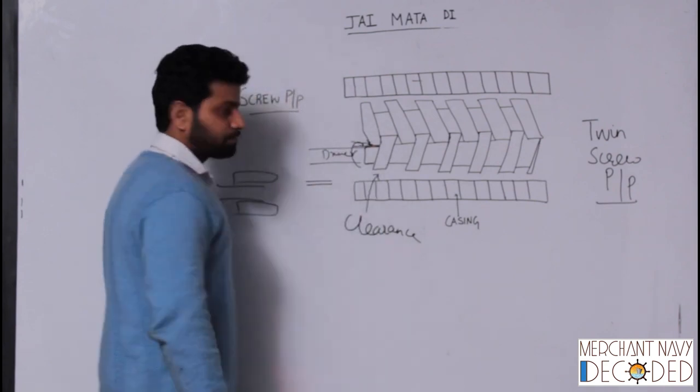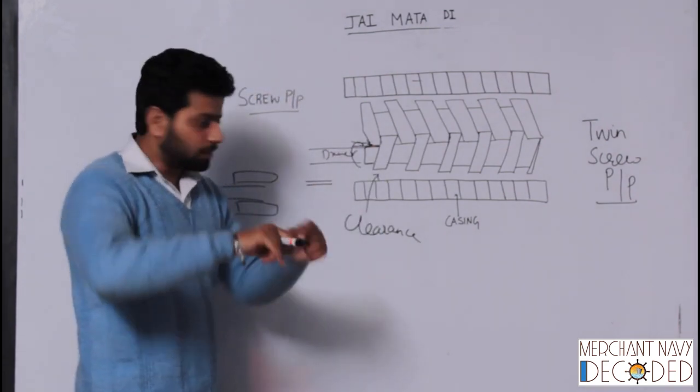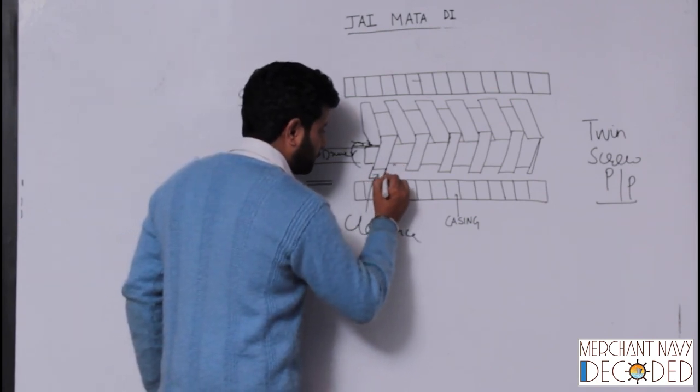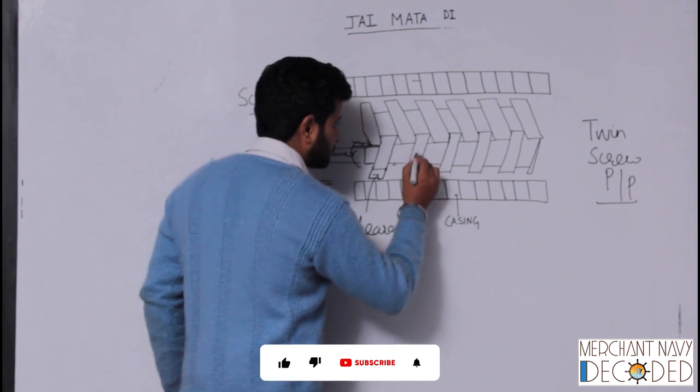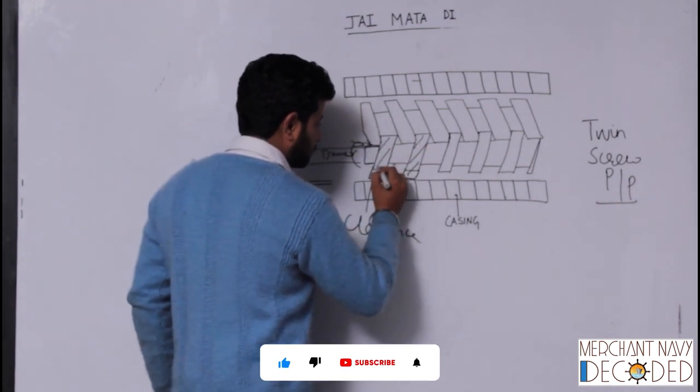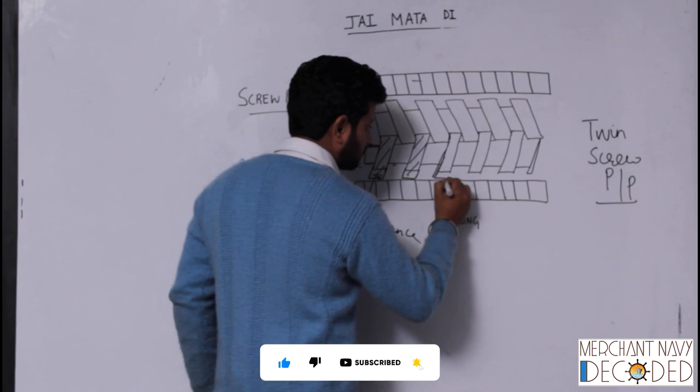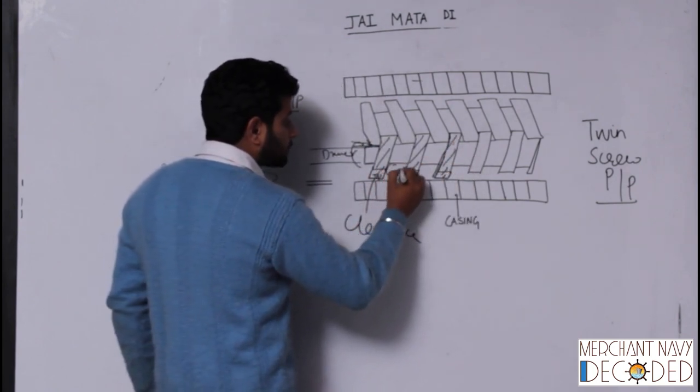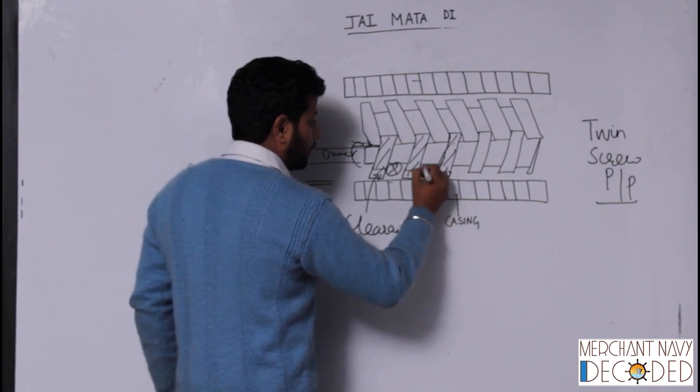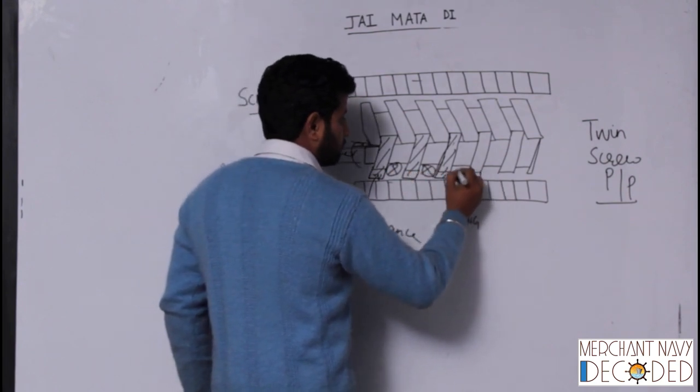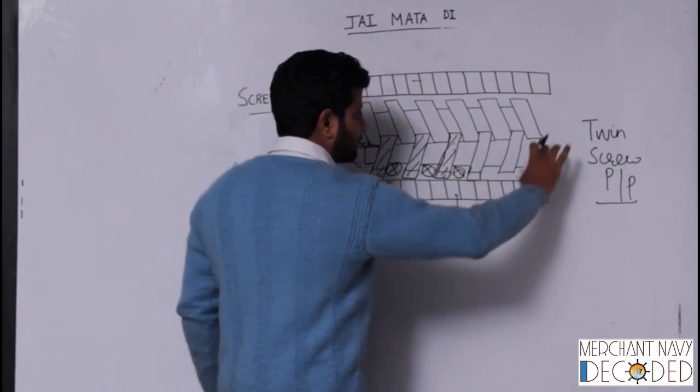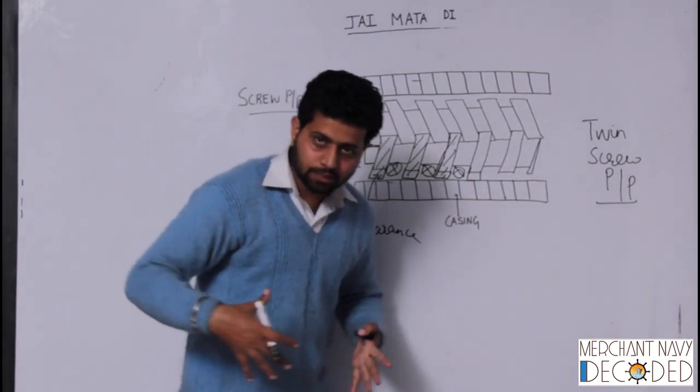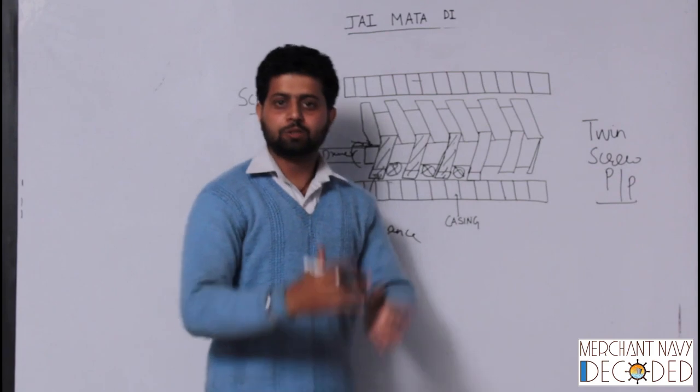And when it rotates, oil is trapped over here. So let me show you the current platform. It is like this: the clearance is less, oil is over here, oil is over here, oil goes over here. And when it reaches over here, again as in gear pump, the area reduces and discharge takes place because pressure increases.